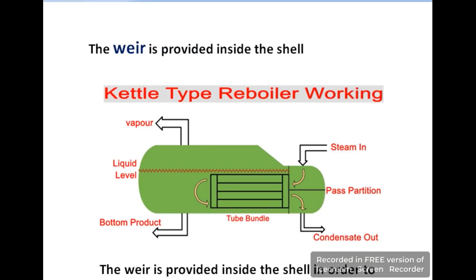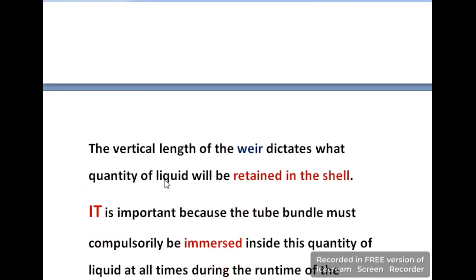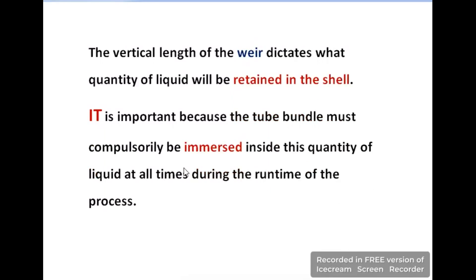A weir is also provided in the shell, and its role is to control the level of the liquid by exiting excess liquid from the shell. The vertical length of the weir dictates what quantity of liquid will be retained in the shell, because it is important that the tube bundle must remain immersed in some quantity of liquid at all times during the running of the process.